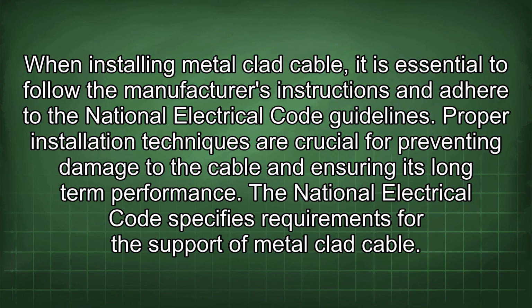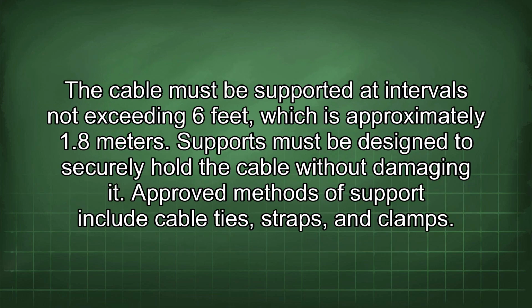When installing metal-clad cable, it is essential to follow the manufacturer's instructions and adhere to the National Electrical Code guidelines. Proper installation techniques are crucial for preventing damage to the cable and ensuring its long-term performance. The National Electrical Code specifies requirements for the support of metal-clad cable. The cable must be supported at intervals not exceeding 6 feet, which is approximately 1.8 meters. Supports must be designed to securely hold the cable without damaging it. Approved methods of support include cable ties, straps, and clamps.